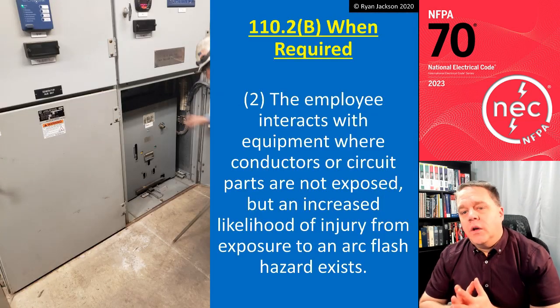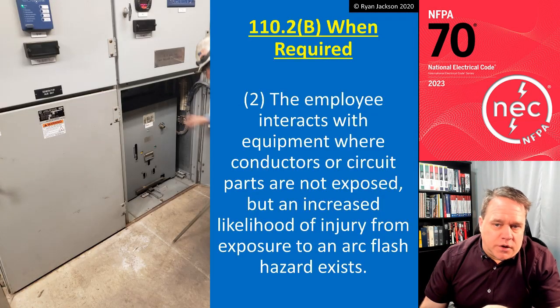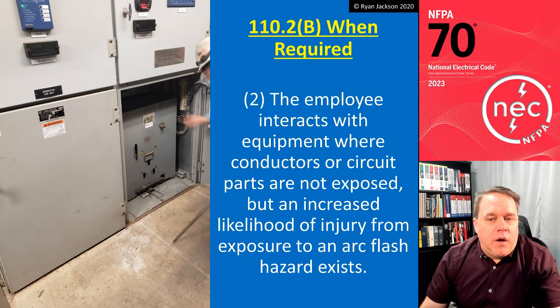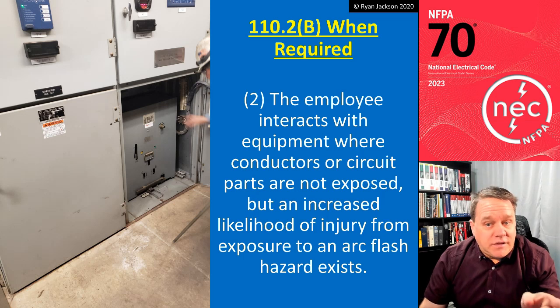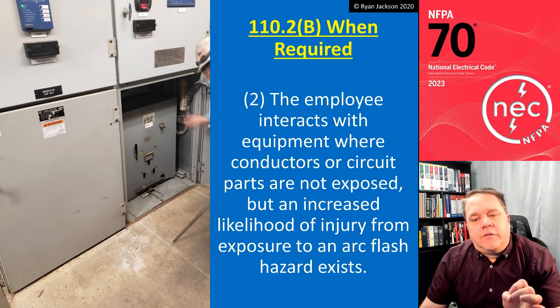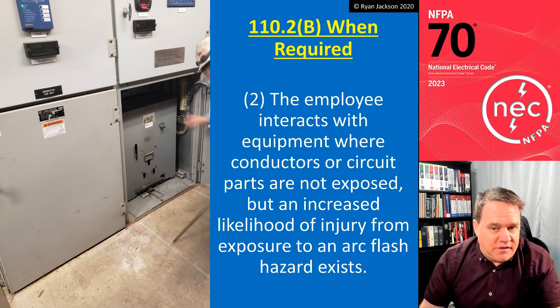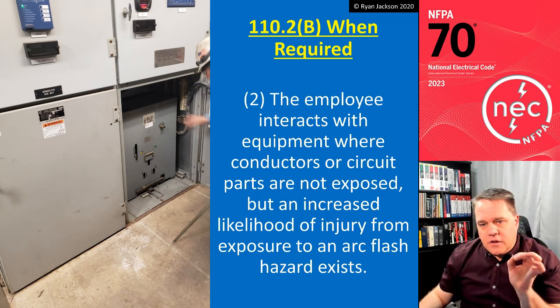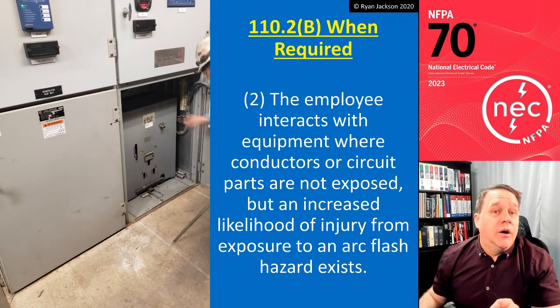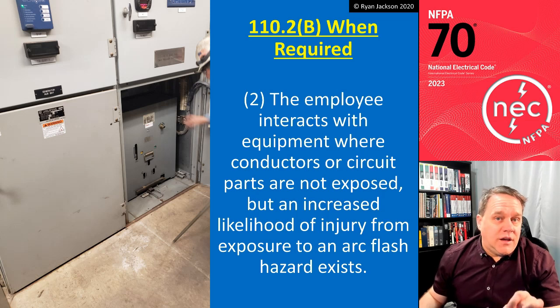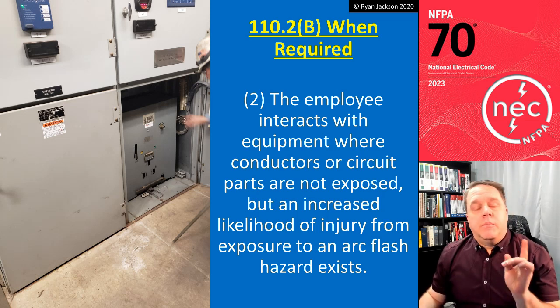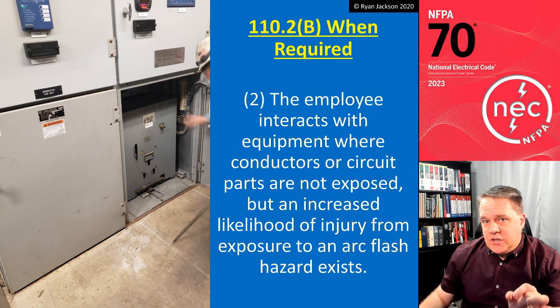Or item 2, I have to have an electrically safe work condition if the employee interacts with equipment where conductors or circuit parts are not necessarily exposed, but an increased likelihood of injury from exposure to an arc flash hazard exists. Okay, if the circuit conductors or circuit parts are not exposed, then there's not a shock hazard, right? An electric shock hazard. But could there still be an arc flash hazard?